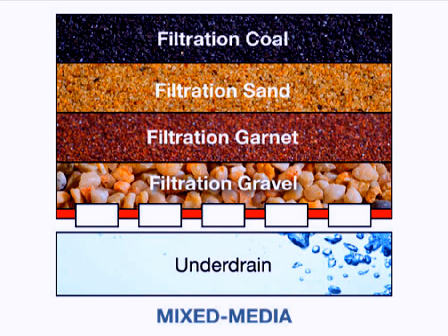Garnet sand. Garnet sand, or ilmenite, is used as the bottom medium in multimedia filters. It is graded to be finer than sand, but because of its greater density, it tends to stay at the bottom of the filter.